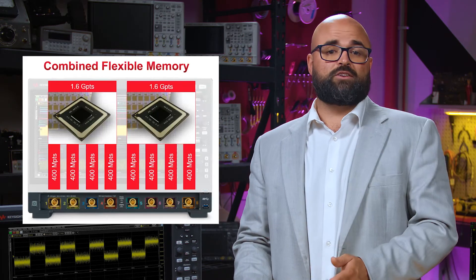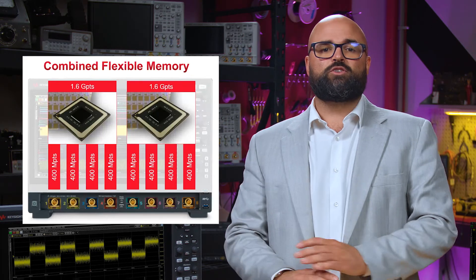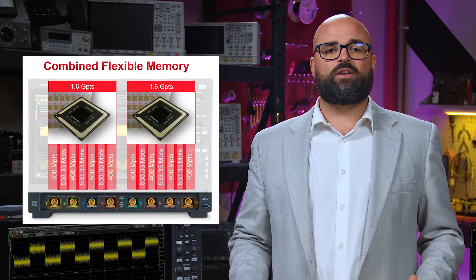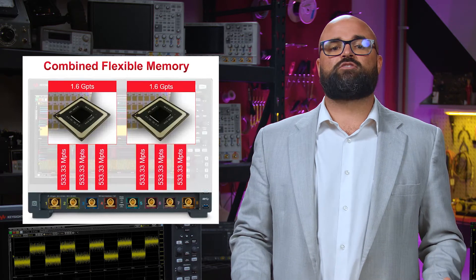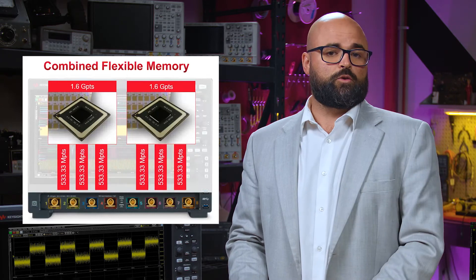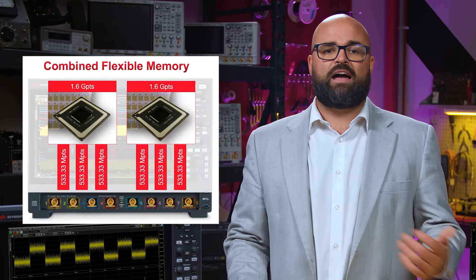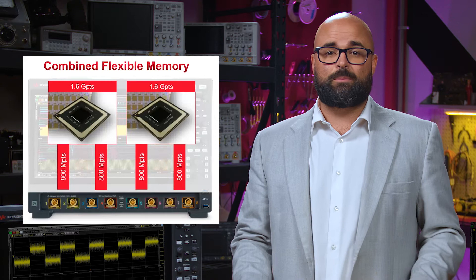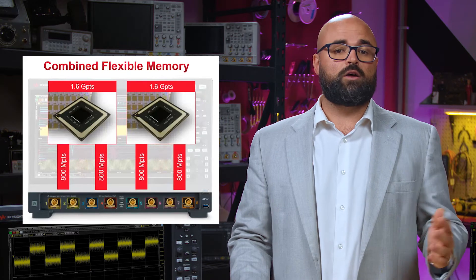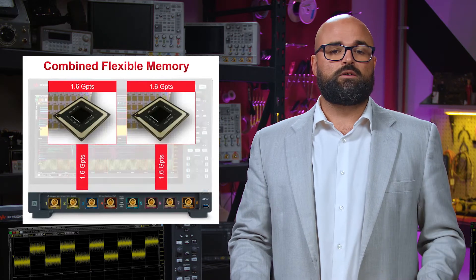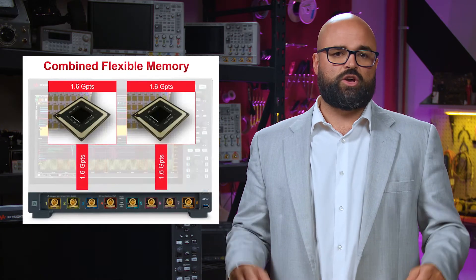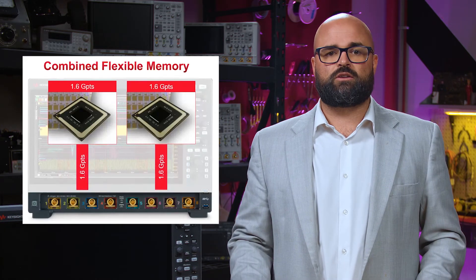With combined flexible memory, total samples can be increased as channels are disabled, for a maximum of 1.6 gigasamples available on one channel, or on two channels for 8 channel oscilloscope models.